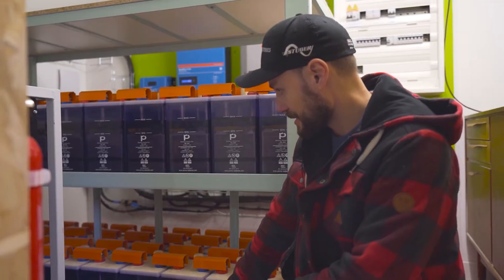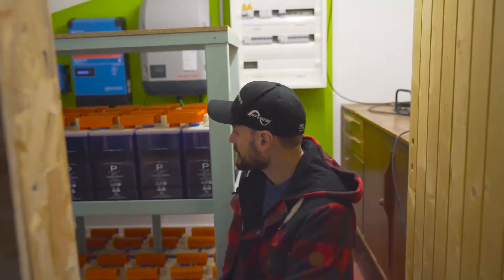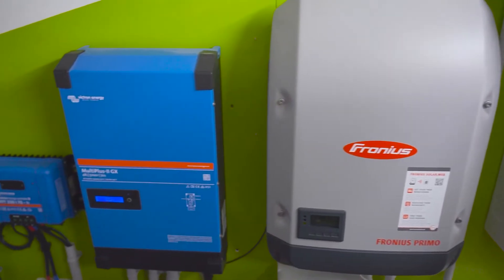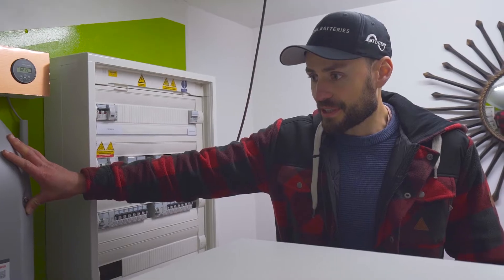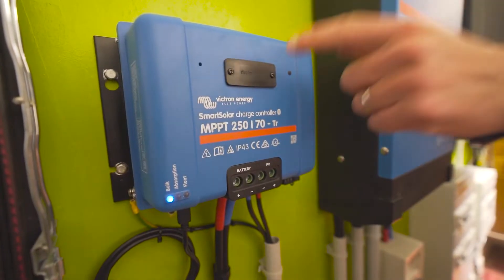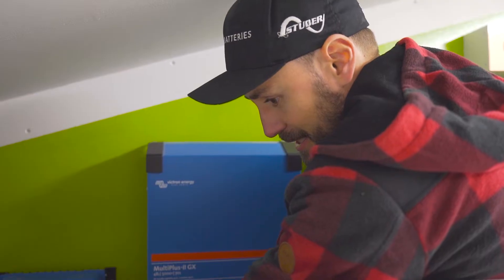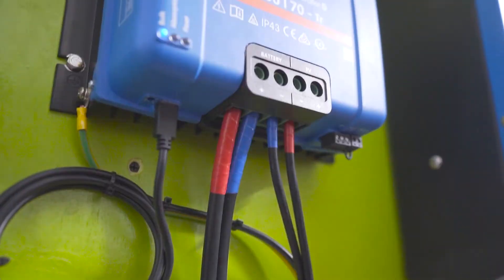So we're looking at 15 kVA of capacity. This battery system is connected to the power conversion system on a Victron plus Fronius platform. From the smallest to the largest, we have an MPPT charger which controls five solar panels on the roof, with two main functions: recharging the batteries, and also via the multi-plus inverter stage, supplying daytime consumption.